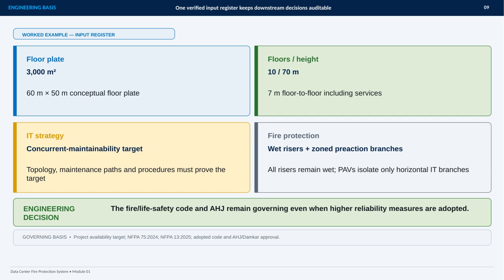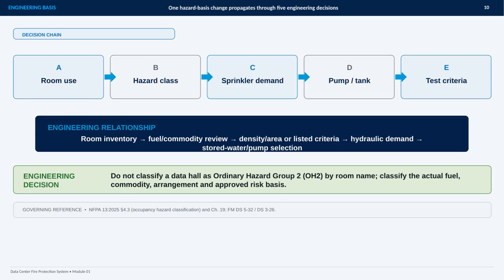Finally, the governing decision is clear. Adopting higher reliability measures does not replace the Fire and Life Safety Code or the authority having jurisdiction. The design remains governed by the Project Availability Target, NFPA 75:2024, NFPA 13:2025, the adopted code, and AHJ/Damkar approval. This slide establishes the engineering basis for the fire protection design.